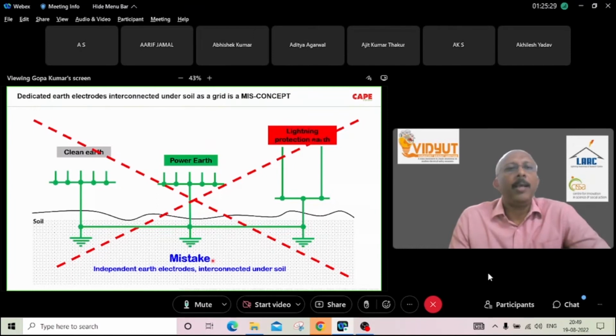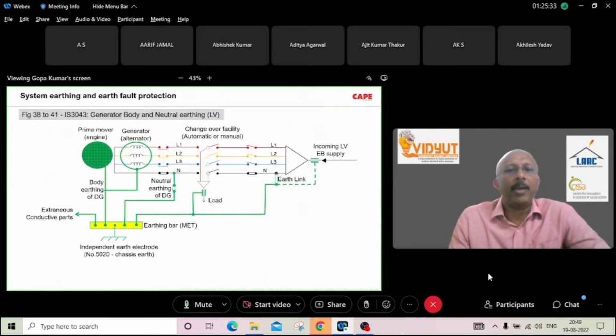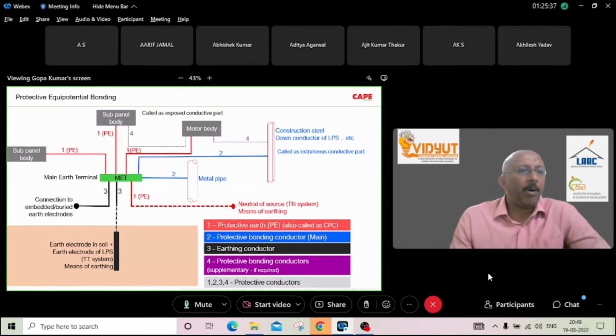So the only written method which has to be followed is called protective equipotential bonding. Means all the metallic parts in your building are interconnected together in such a way that simultaneously accessible metallic parts don't carry a shock voltage. As a result, people are safe.